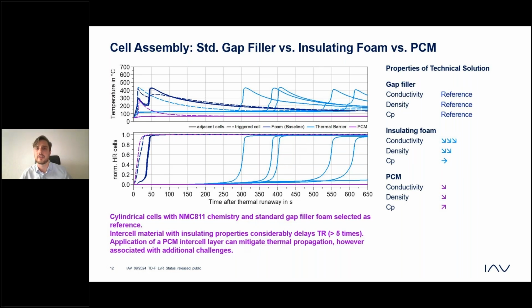As a different material, we have been checking also an insulating foam, which is the blue curves. The insulating foam compared to our reference gap filler has a lower conductivity, a lower density, and a similar CP value. And we can see that the neighboring cells are triggered later, so delayed compared to our reference case. So the insulating foam works to at least delay the thermal propagation. The same is visible also here in the heat release curves.